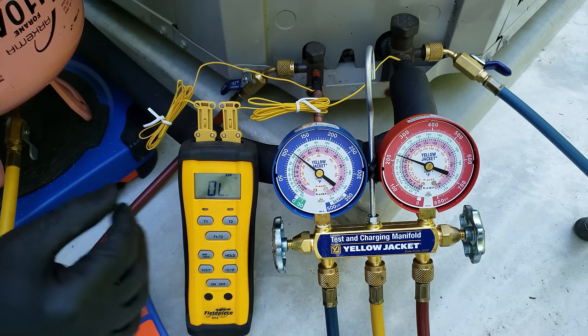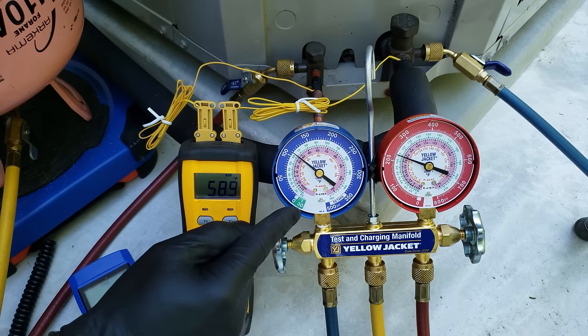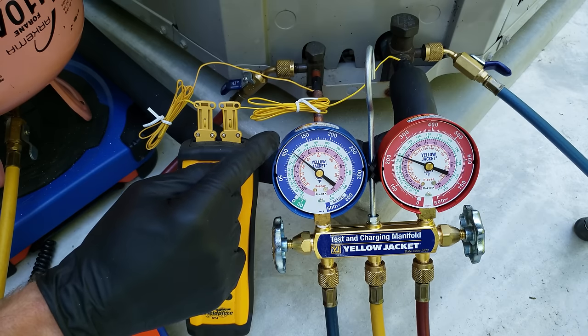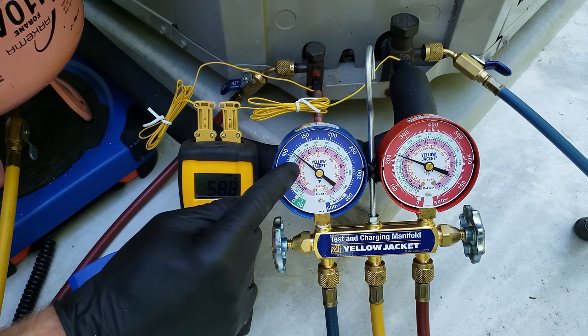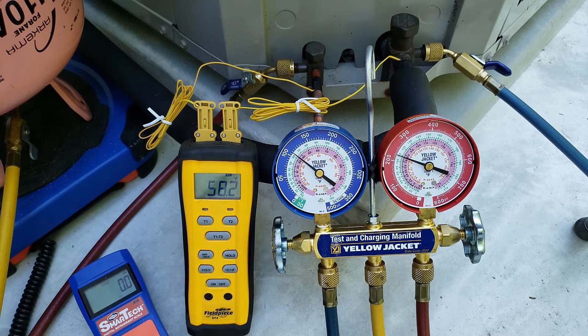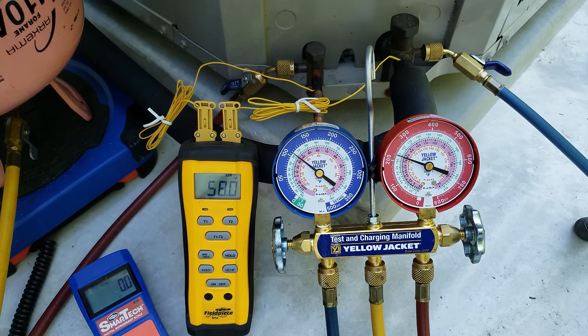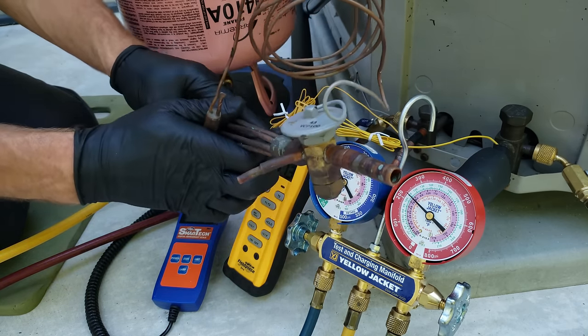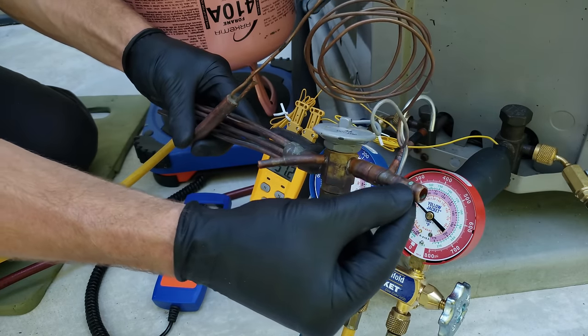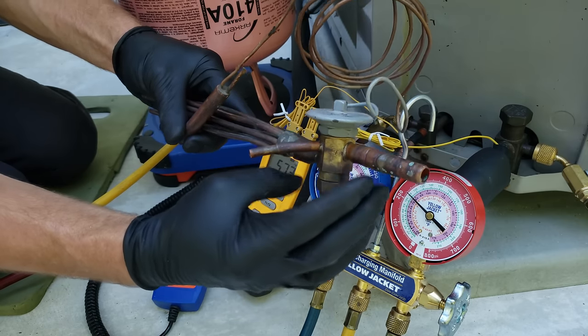Let's also check our total superheat. We have about 58 degrees on the vapor line temperature and about 110 psi on the large vapor line. Converted to saturated temperature, that's 35 degrees. So 58 minus 35 gives us 23 degrees of total superheat — that's total superheat because we're measuring it at the outdoor unit. A TXV should be able to handle about 8 to 14 degrees across the indoor coil. With no subcooling, we do not have liquid-only heading to the TXV — we have a little vapor mixed in with liquid. So we need to add refrigerant to this system.